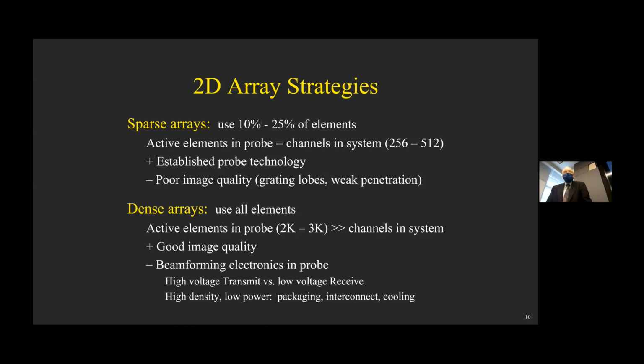The alternative is to make arrays that are fully dense, typically with element counts that start off in the area of 2,000 to 3,000 elements in the system. That's a lot more than the number of channels in the system. So you end up having to put some kind of beamforming electronics into the probe.